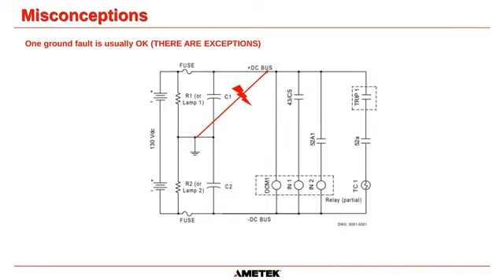And actually what you see here is a really old-fashioned tripping and closing circuit, and each circuit has its own ground fault detection on it. They've got their own potential divider here using a lamp. That's all these resistors are doing. So if you get one fault on the system, not a problem. All it means is now the positive bus is referenced to ground. No high current is going to flow. Nothing's going to break. Usually it's all fine.